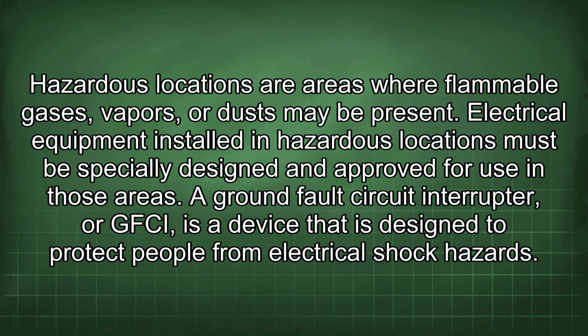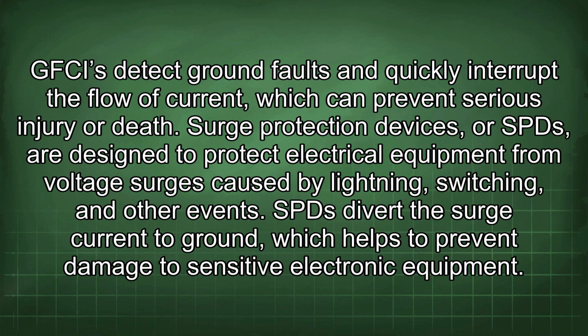A ground fault circuit interrupter, or GFCI, is a device that is designed to protect people from electrical shock hazards. GFCIs detect ground faults and quickly interrupt the flow of current, which can prevent serious injury or death. Surge protection devices, or SPDs, are designed to protect electrical equipment from voltage surges caused by lightning, switching, and other events. SPDs divert the surge current to ground, which helps to prevent damage to sensitive electronic equipment.